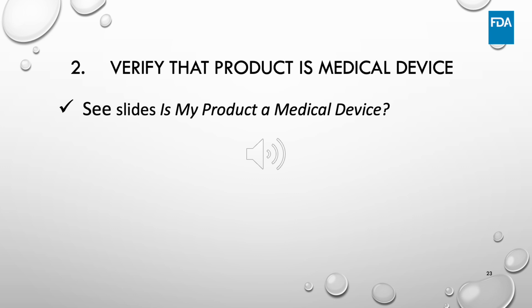Once you have established these details, the next step is to confirm that the product is a medical device. This step may sometimes appear to be unnecessary if it's already obvious that the product is a medical device. However, this is not always the case. For example, the device may be a combination product. For more detail, refer to the slides, Is my product a medical device?